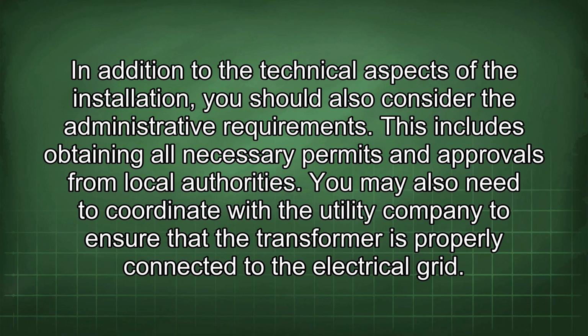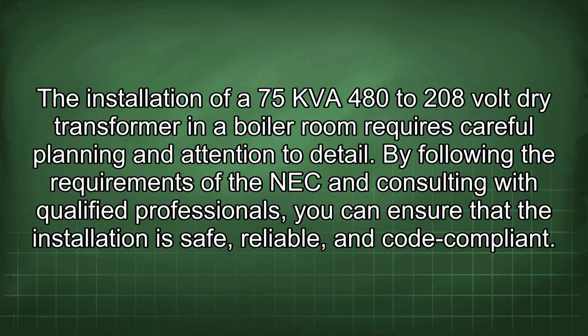In addition to the technical aspects of the installation, you should also consider the administrative requirements. This includes obtaining all necessary permits and approvals from local authorities. You may also need to coordinate with the utility company to ensure that the transformer is properly connected to the electrical grid.